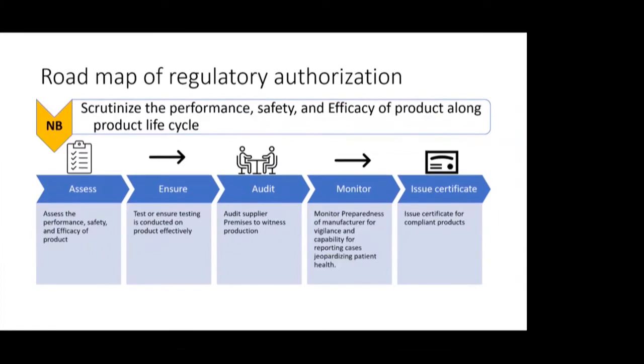I think we are ready now for a small journey into how the notified body handles the documentation when it receives it from the manufacturer. They start by assessing the performance, safety, and efficacy of the product by reviewing the documentation, the technical file, and they have specific experts to review everything. For example, if the device is sterile, there is specific expertise at the notified body premises to review this. They also have clinical experts to make sure the product documentation is compliant with the requirements. Then they ensure that the tests on the product are effectively conducted, including the capability of the lab conducting the testing.